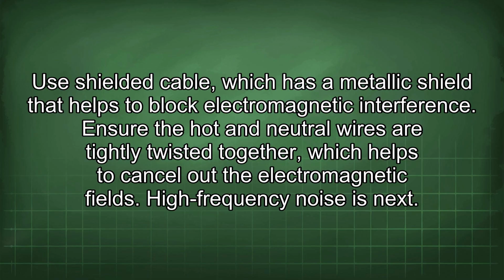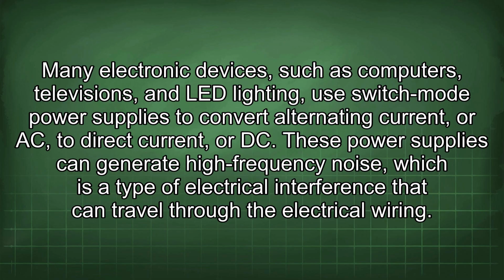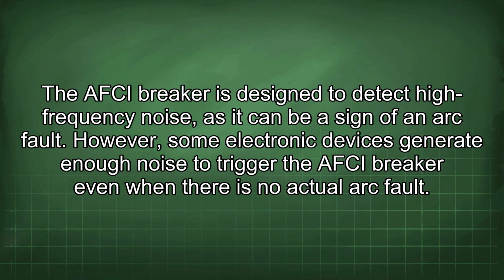High-frequency noise is next. Many electronic devices, such as computers, televisions, and LED lighting, use switch mode power supplies to convert alternating current, or AC, to direct current, or DC. These power supplies can generate high-frequency noise, which is a type of electrical interference that can travel through the electrical wiring. The AFCI breaker is designed to detect high-frequency noise, as it can be a sign of an arc fault. However, some electronic devices generate enough noise to trigger the AFCI breaker even when there is no actual arc fault.